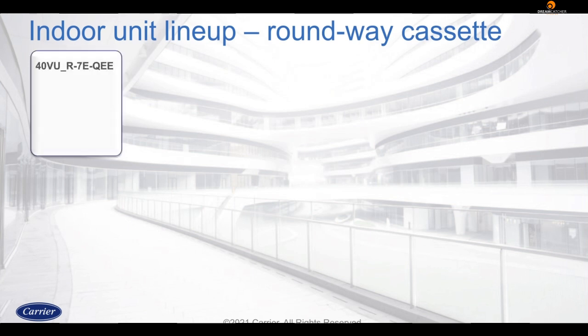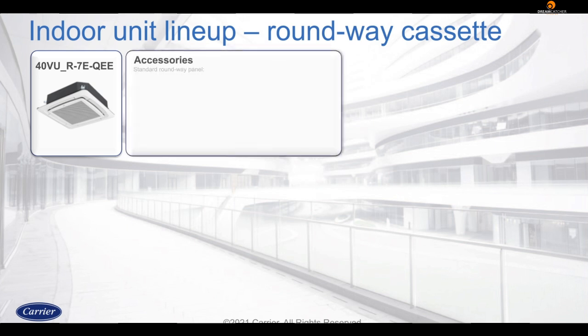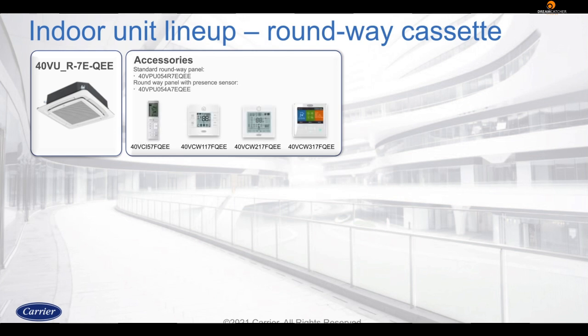Before looking at the lineup, let's understand the nomenclature. All indoor units start with 40. V stands for VRF, and the next letter depicts the type of indoor unit. In this case, U refers to a round-way cassette. The next number stands for the capacity, and this is followed by the unit type. R here represents round-way cassette. Next, the 7 stands for 7th generation VRF technology, and E depicts the kind of power supply. The next symbol denotes the country of origin, in this case Q, which means China. The last 2 symbols denote the region for which that particular model is made. In this case, EE stands for both Europe and Asia.